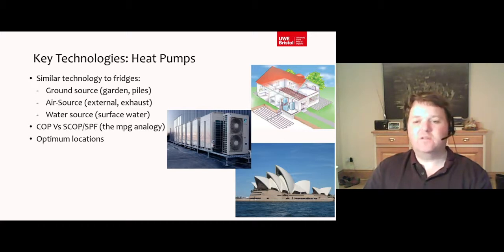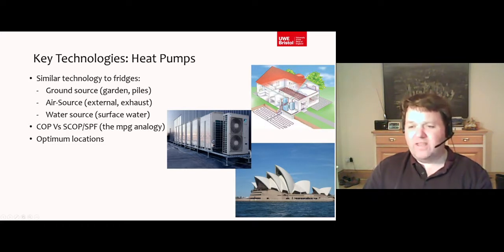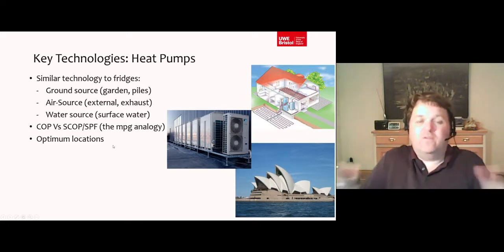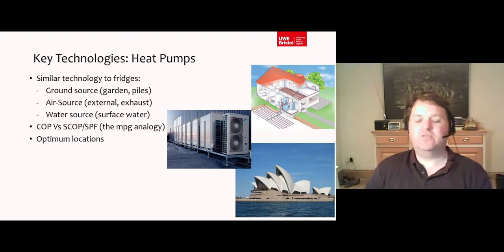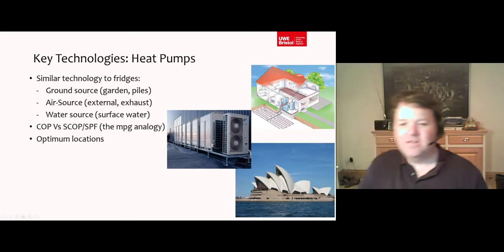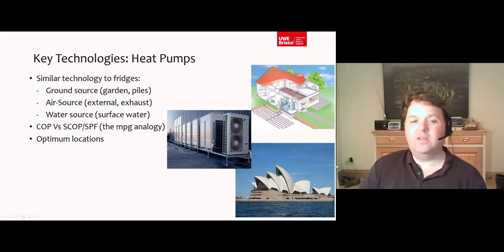What can influence the efficiency of a heat pump? One factor is its optimum location — where the heat enters the system. Whether it's in your garden or in the air, it likes to have a lot of flow across that heat emitter. An air source unit exposed on a roof with lots of air going through it is ideal. If you put it down on the ground and place a hoarding around it, that limits airflow and efficiencies will change as a result. Similarly for ground source, if you put it in the wrong location or the wrong type of soil, you don't get adequate heat flow into it.